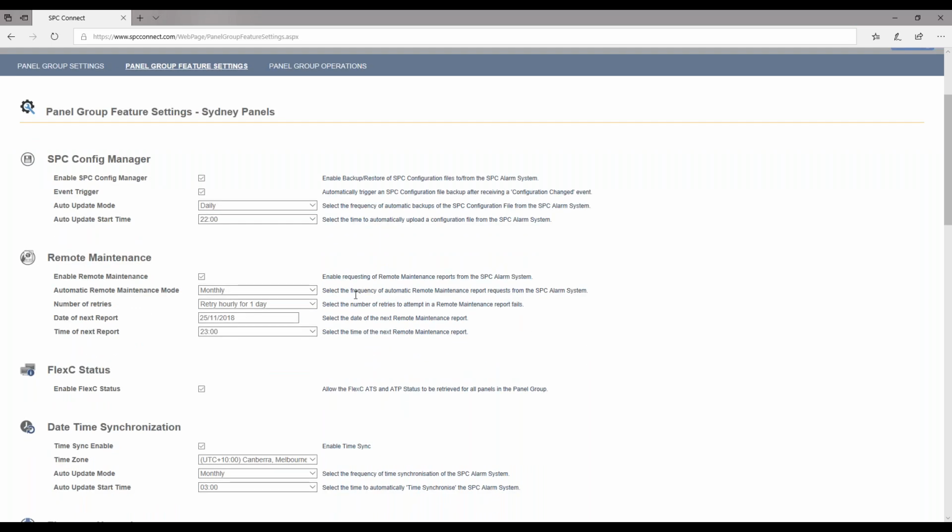Every month we upload a remote maintenance report. We'll have a look in a sec what is included in that report, but we can see here every month at 2300 it will upload an remote maintenance report for every panel in this group that we can review at our leisure.